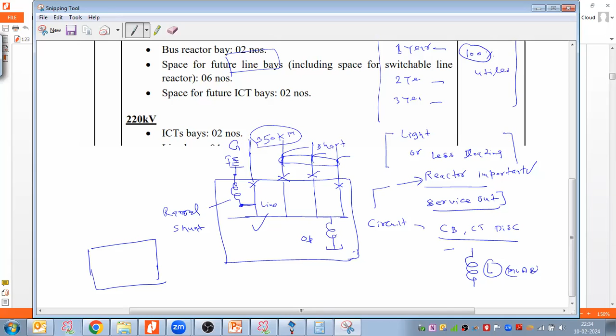So we have two choices: either we connect with the line, or we connect with the bus. Suppose we have many transmission lines, and we see that one is a longer transmission line - instead of putting a reactor on each line bay, I will place one common reactor on the bus bar only. But if I see that only one particular line has higher length while others are not so long, then I will connect the reactor directly with that particular circuit instead of putting it on the bus. But anyway, this decision is not taken by the design engineer alone.